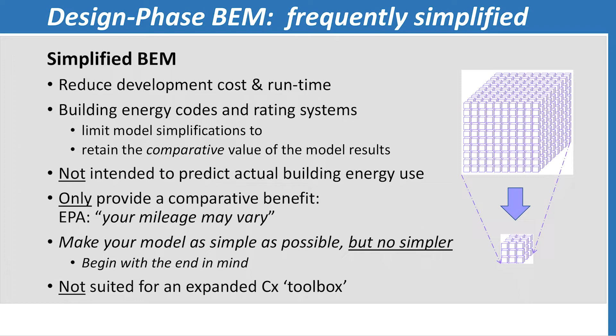With design phase, pre-occupancy, it is common practice to simplify, maybe significantly, and what we're concerned about, for purposes of including it in the CX toolbox, is that the BEM model itself is oversimplified too often. That's done largely to reduce the cost of the modeling, and to reduce the runtime so you can turn it around and get quicker answers.